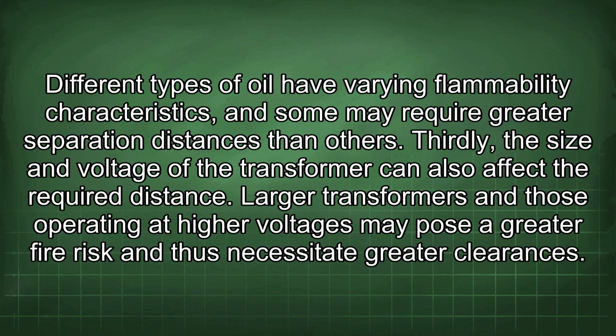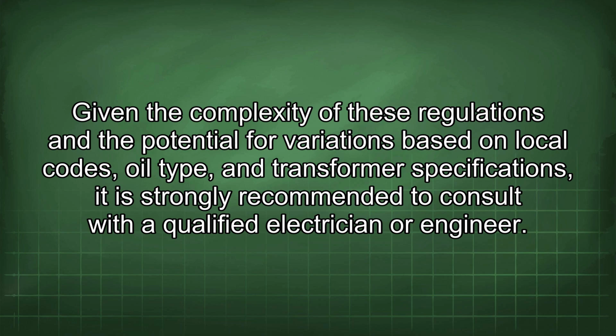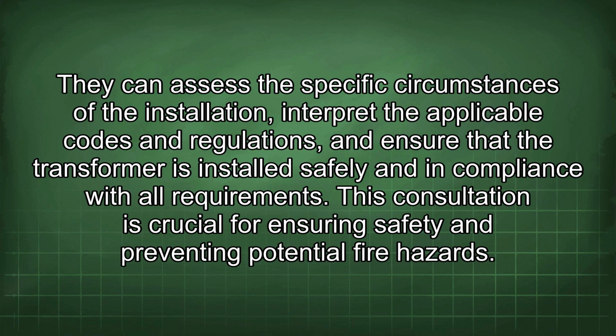Thirdly, the size and voltage of the transformer can also affect the required distance. Larger transformers and those operating at higher voltages may pose a greater fire risk and thus necessitate greater clearances. Given the complexity of these regulations and the potential for variations based on local codes, oil type, and transformer specifications, it is strongly recommended to consult with a qualified electrician or engineer. They can assess the specific circumstances of the installation, interpret the applicable codes and regulations, and ensure that the transformer is installed safely and in compliance with all requirements. This consultation is crucial for ensuring safety and preventing potential fire hazards.